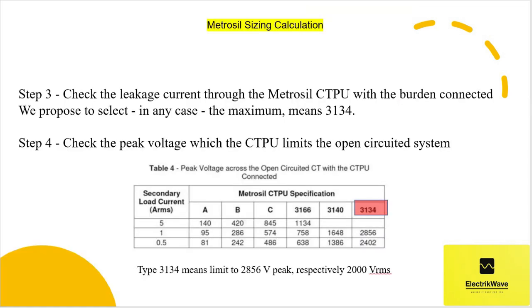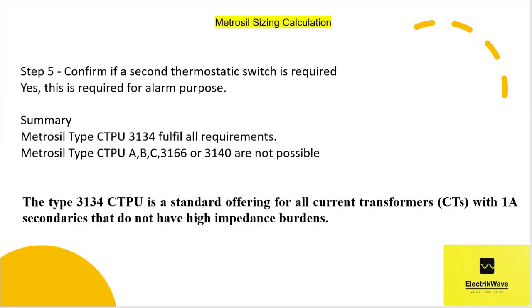Next. Step 3. Check the leakage current through the Metrosil CTPU with the burden connected. We propose to select in any case the maximum, meaning 3134. Step 4. Check the peak voltage which the CTPU limits the open-circuited system to. Type 3134 means a limit of 2856 volts peak, respectively 2000 volts RMS. Next. Step 5. Confirm if a second thermostatic switch is required. Yes, this is required for alarm purposes.